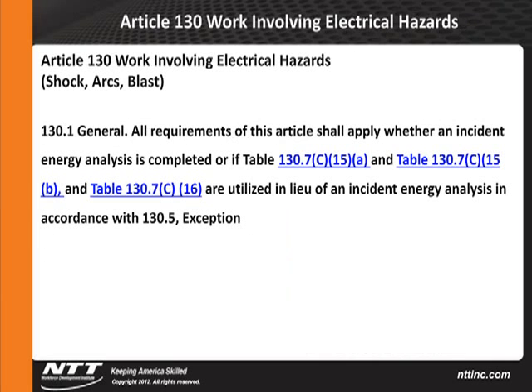Another area that's been updated recently is going to deal with the charts that were available in 2009. The charts in the 2009 edition basically dealt with AC voltages. So it says general. All requirements of this article shall apply whether an incident energy analysis is completed or if Table 130.7(C)(15)(A) or (C)(15)(B) is used. That's for AC and DC, and then the clothing that goes along with it. So what do those tables look like today? Let's see if we can find them here.